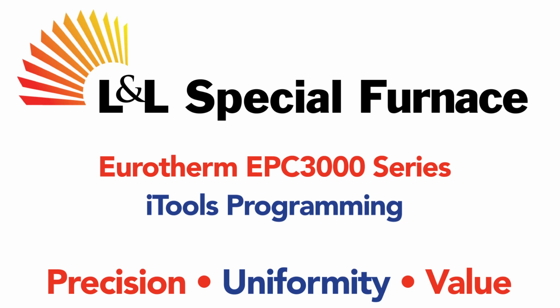In this video, we're going to demonstrate how to configure a heating profile for a Eurotherm EPC3000 series program controller via the Eurotherm iTools software. The iTools software is given away complimentary by Eurotherm, but it does require a special USB cable. L&L Special Furnace provides this USB cable with any EPC controller.